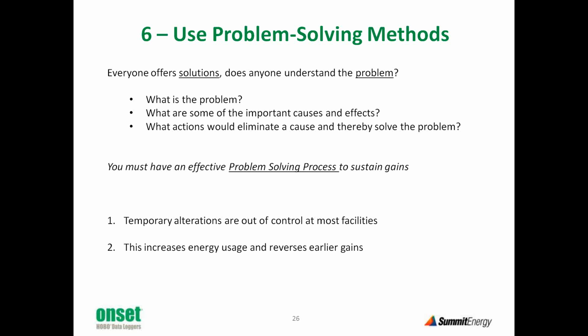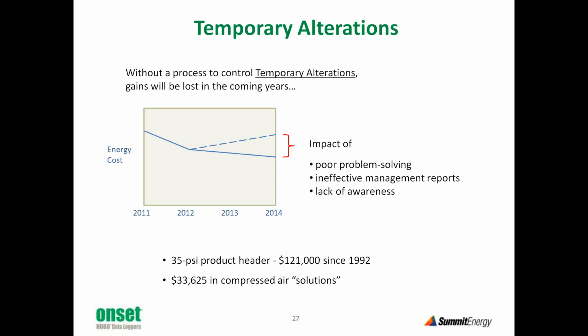So I'm not saying that those floor mechanics shouldn't go jam that board in if it helps us get the line back up and running. They should still do that. But somebody should report that temporary alteration so that the control of the air handlers and ventilation and control of condensate in the plant can be carefully understood so we can see, well, you know what, let's go change the program in this PLC, or let's put a fan over here, and let's go take that 2x4 out of the dampers. If you don't get control of that, what happens is you go implement different energy conservation measures, you see a reduction in energy, but then in subsequent years it creeps right back up again.